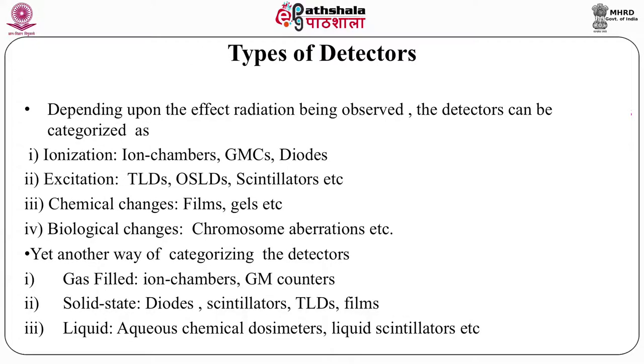What types of detectors are available? Depending upon the effect of the radiation being observed, detectors can be categorized as ionization-based detectors — the most popular among them are ion chambers, Geiger-Müller counters, and semiconductor diodes. Then there are detectors based on the excitation caused by radiation: thermoluminescent detectors (commonly known as TLDs), optically stimulated detectors (OSLDs), and scintillator detectors.